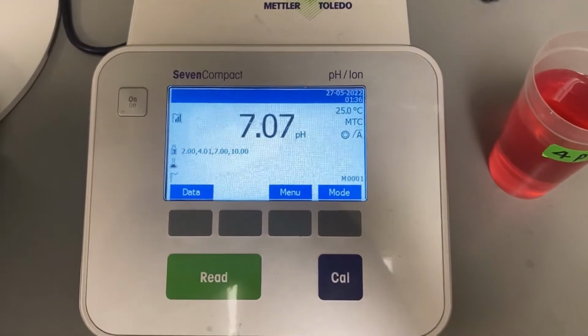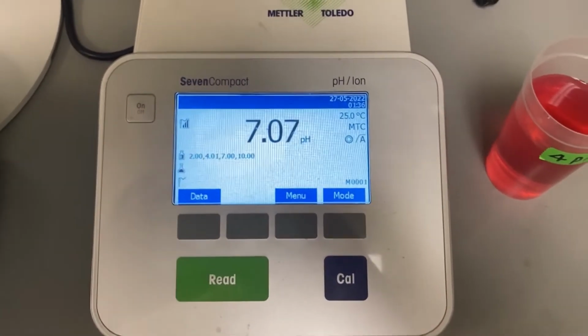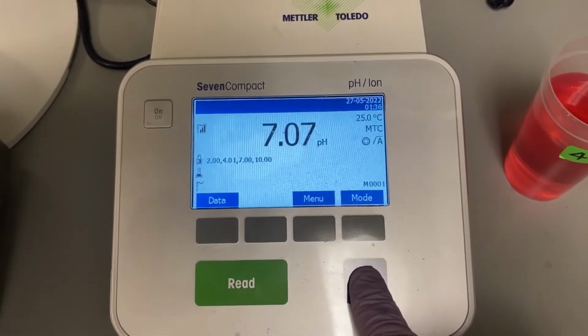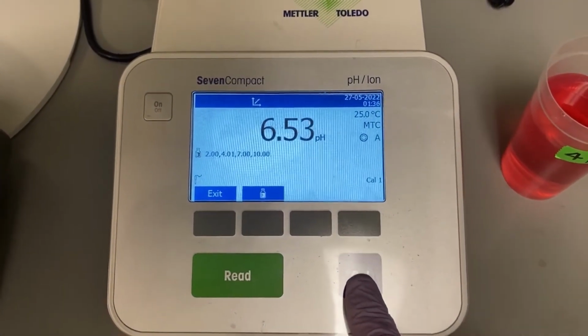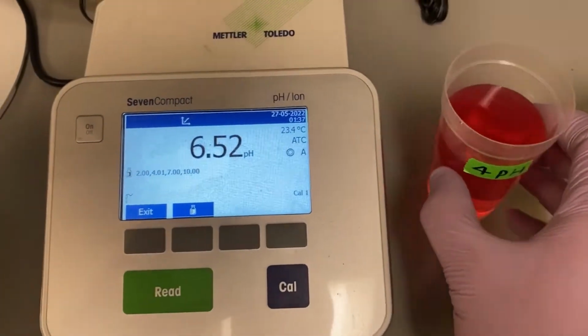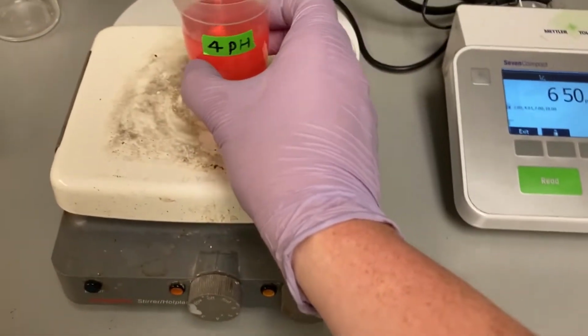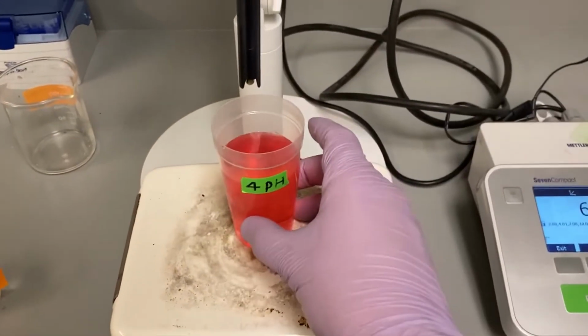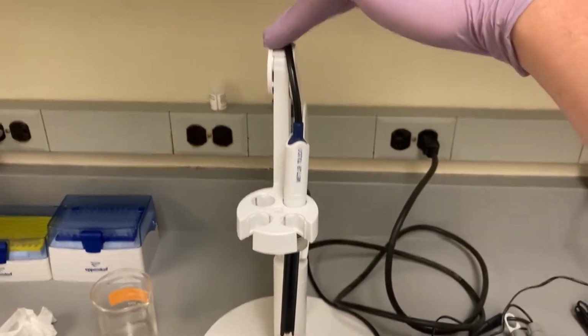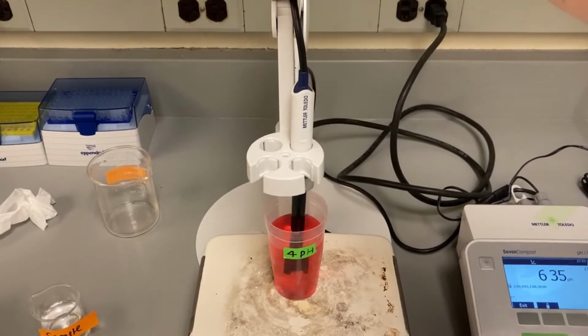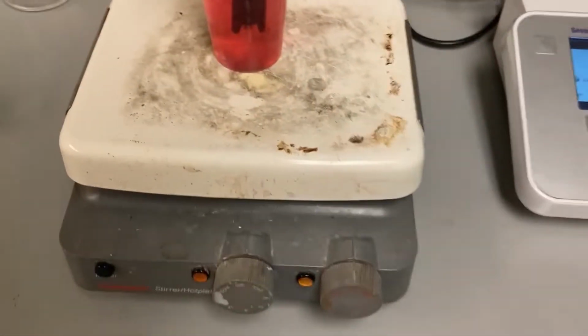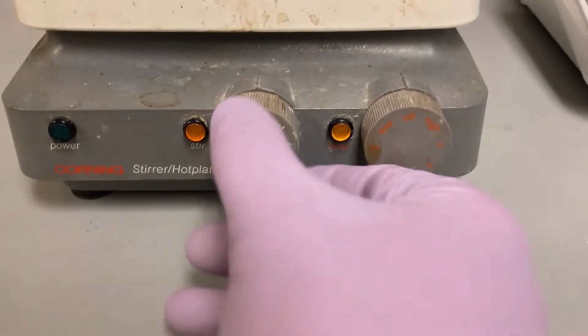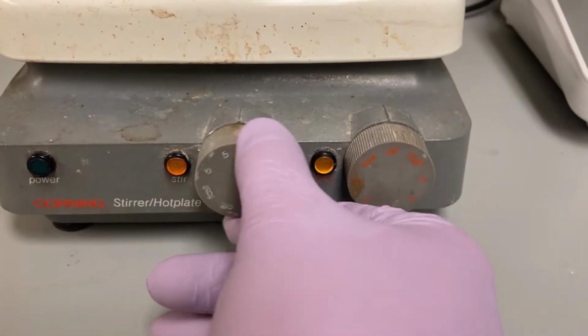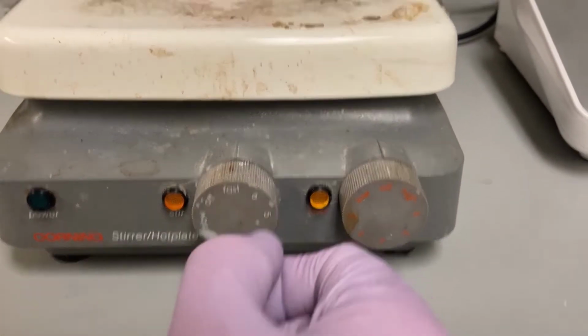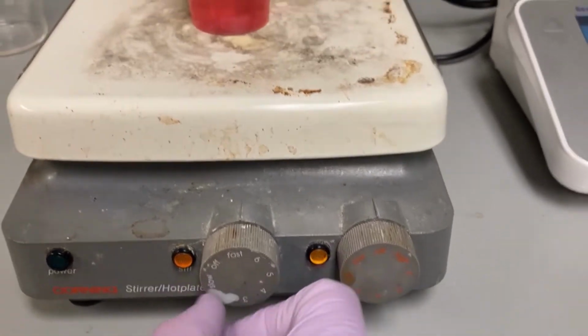When you turn the probe on, this menu will appear. You want to hit calibrate. And now you can put the first buffer on, which will be the 4. You can just press down and the probe will be held in the solution. And then I'm going to turn on the stir rod. Depending on the size of the stir rod, you might have to mess with the speed.